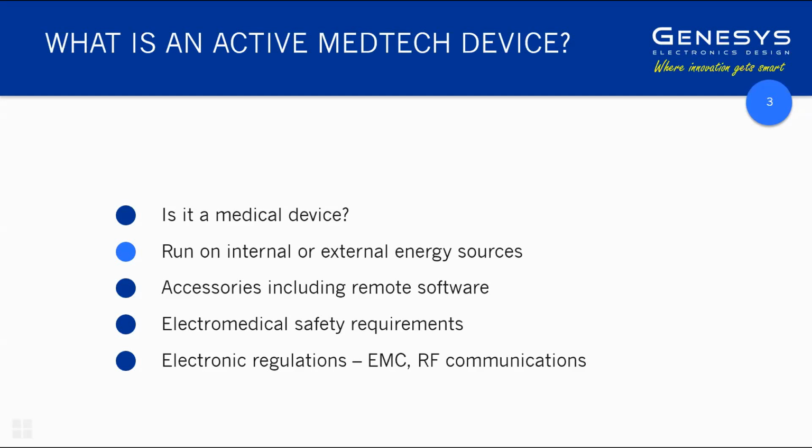It's important to note that any accessories connected to that device, including any remote software that's important in the running of that device, is also a medical device, even if it's completely independent. Software as a medical device in its own right is another subject we'll be delving into later.